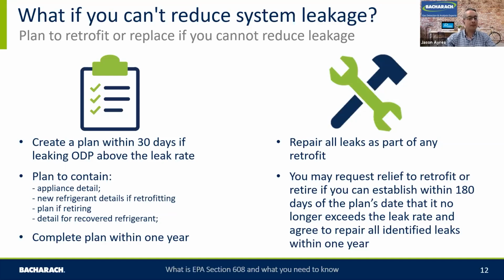But what it does mean is you need to have a good system to capture that information. You need to be aware of your requirements. You need to be aware of what leakage rates are and capture that. You need to be aware that you need to keep inspections. And if you can't keep that reduction level down, you need to come up with a plan to stop any further leakage. That's really the fundamentals for being an owner operator of the system. So it's quite onerous, but there is help available for you out there.